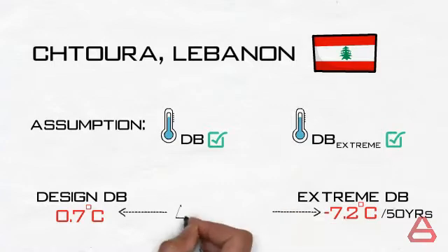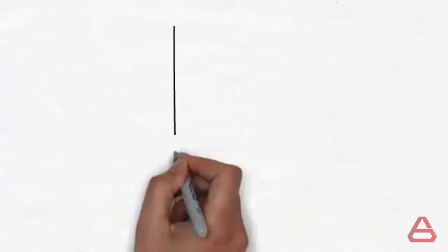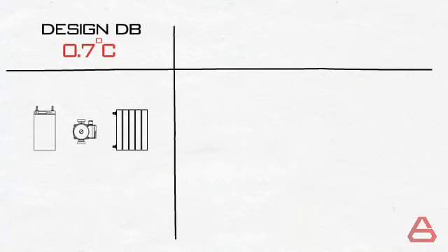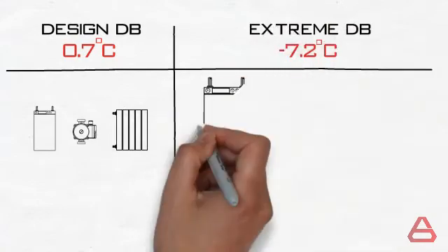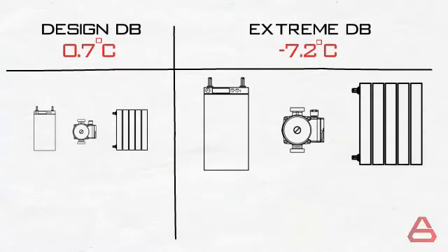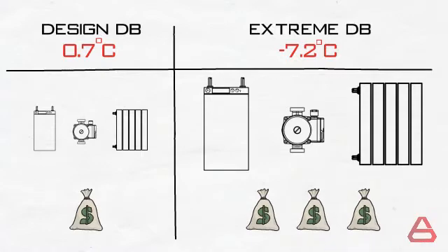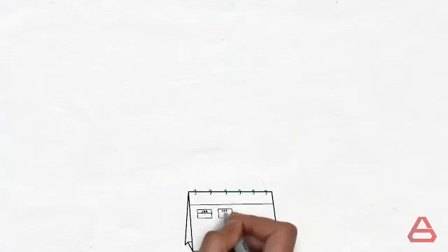This is a humongous difference, a delta T of about 8 degrees. At a design of 0.7 degrees Celsius, the heating system you would have installed and operated would have to be doubled in case of design temperature of minus 7.2 or even more. And the larger system means higher initial and operational costs. But all of this is for what? The minus 7.2 degrees Celsius mentioned is likely to happen every 50 years.